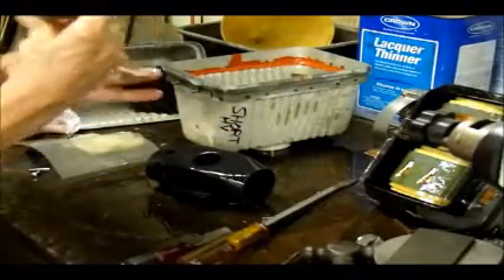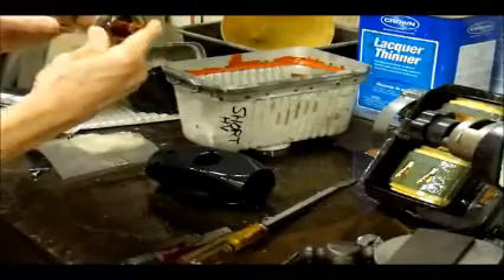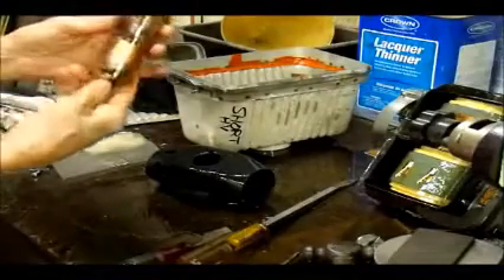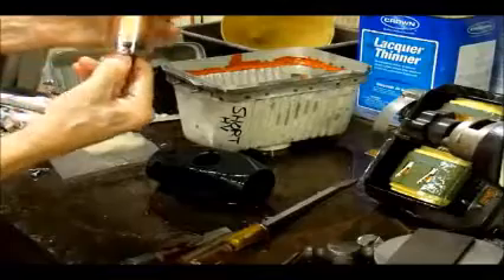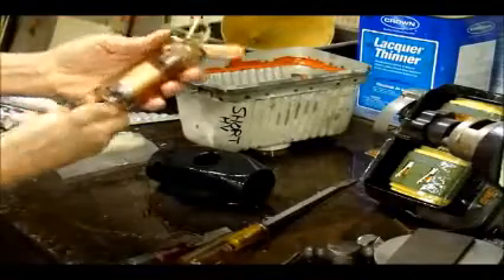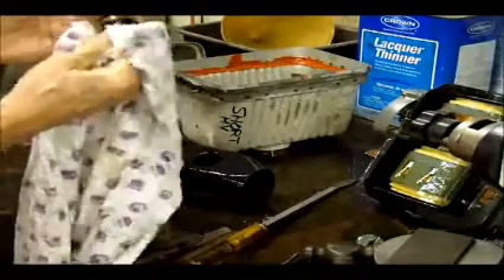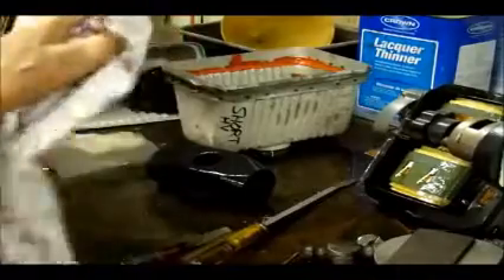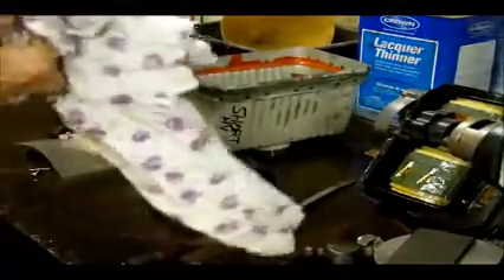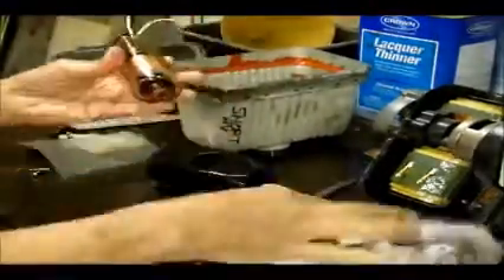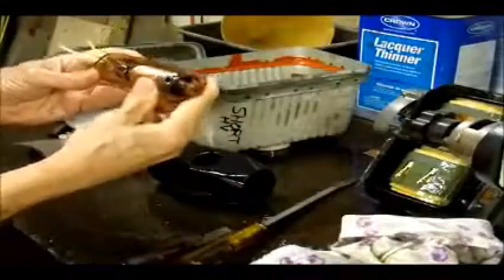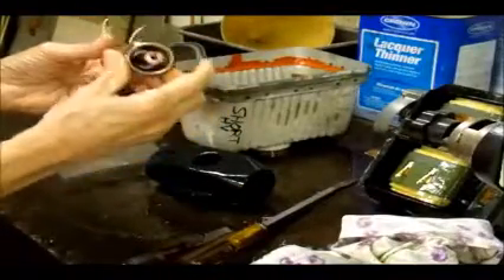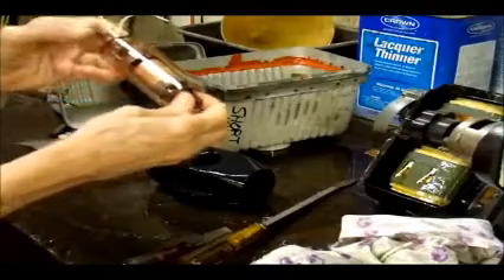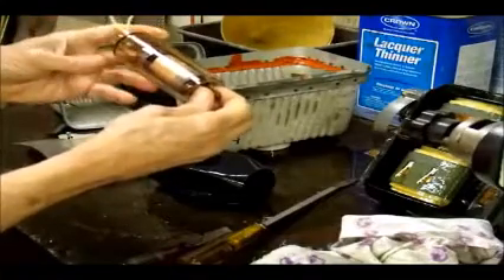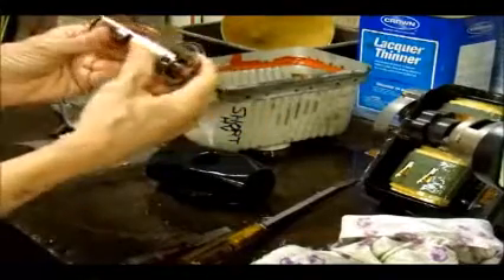The tube looks completely intact. There's no sign of arcing or anything else. That's our little X-ray tube. That's a beautiful little job, isn't it? A tube like this is capable of 150 kilovolts. I mean, you can put 150 kilovolts on it if it's under oil. You can get away with probably on the order of 75,000 with it in the air.